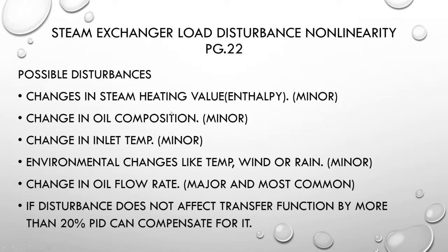Most of these things remain consistent on a day-to-day basis. Generally, when we do production or output changes, we're changing the flow through the plant, which ties in with the oil flow rate. We said earlier, if the disturbance does not affect the transfer function by more than 20%, we can get PID to compensate for it. We just need to be aware of these disturbances and how they potentially affect our decisions on making a control strategy.